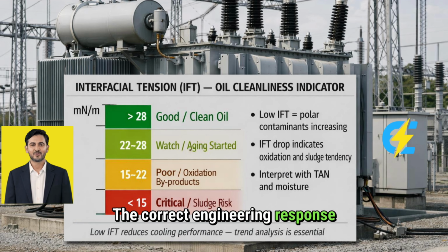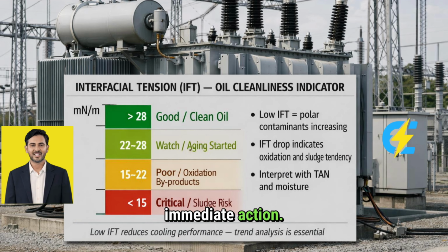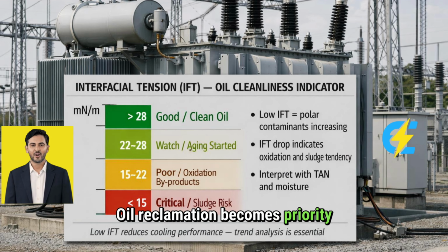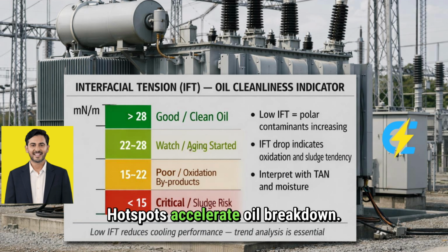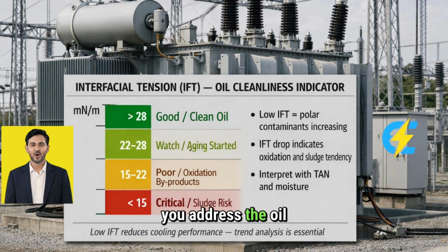The correct engineering response to low IFT requires immediate action. Oil reclamation becomes priority 1. Check your breather and sealing systems. Moisture ingress might be accelerating degradation. Verify your cooling system performance. Hotspots accelerate oil breakdown. Consider load management to reduce thermal stress while you address the oil condition.